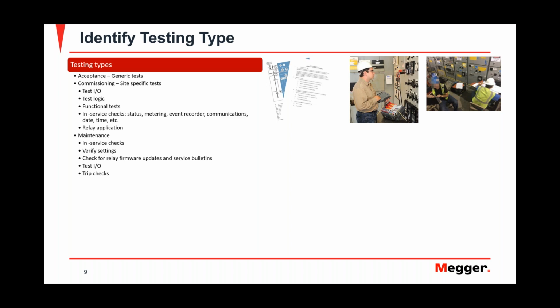I put test the I/Os and do your trip checks. Not so much because the memory of the relay or the logic will change. It's mainly in the mechanical sense. You want to make sure that the wiring between the relay and the IO still operates, that there are no loose connections, that everything from the relay to your trip coil is still working, still in service in the physical sense, not so much in the microprocessor relay world, which is not going to change. That memory is not going to change.